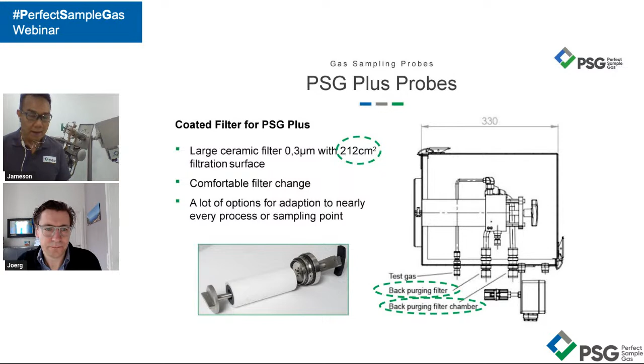The plus probe has two back purges. If you look carefully, the red and also the green. So why is it necessary to have two back purges? Now, there are areas where the particles are higher than many times expected. The first back purge is to clean the surface of the sample filter once it's pulsed out, because many times when we do a back purge, we are talking about not the amount of flow, but the amount of pressure. We want a pulsating, high pressure.